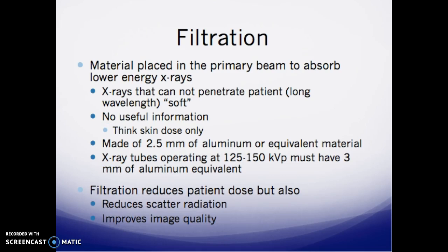Filtration refers to materials placed in the primary beam to absorb low-energy x-rays — long-wave or soft x-rays that cannot penetrate the patient and contribute only skin dose. Filtration is made up of 2.5 millimeters of aluminum or equivalent material. X-ray tubes operating at 125 to 150 kVp must have 3 millimeters of aluminum equivalent.